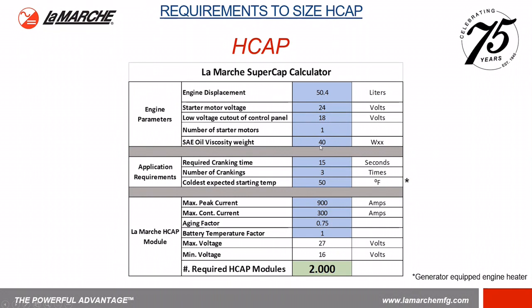Now, this is really important because all engines, as you know, when you're in a 0 degree environment and trying to start an engine on a car, it takes a little bit longer because the engine is much colder because of the oil. And oil is friction, and there's a delayed start. Then the duration for the cranking, which is typically 15 seconds per NFPA 110, and you want to make sure you maintain at least 3 cranking cycles.